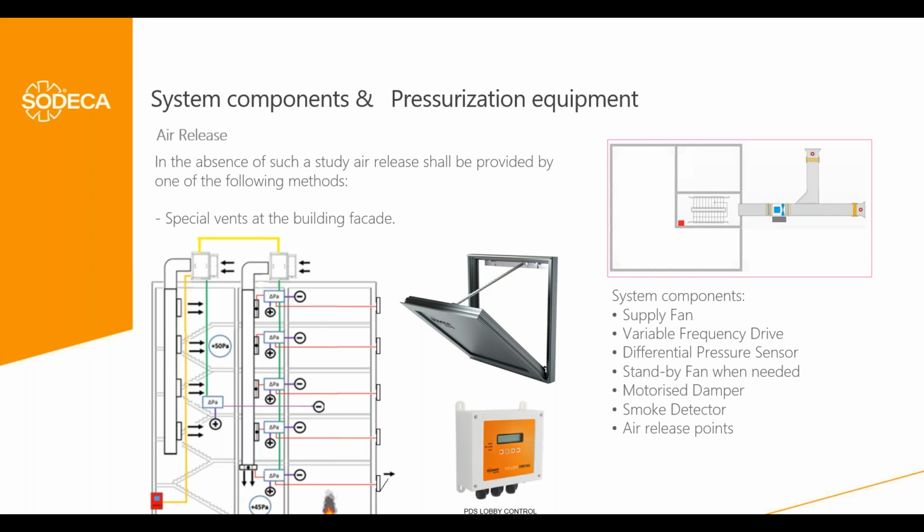Okay, these motorized dampers, flaps, louvers, vents, let's say. In case of these natural vents, if the facades can be affected by the wind, it's necessary to double these vents into facades, with a system reading the velocity and direction of the wind to open or close the proper vent. Okay, we have these possibilities with this type of vents, and we need to open the vent in the fire level, not in the other levels.